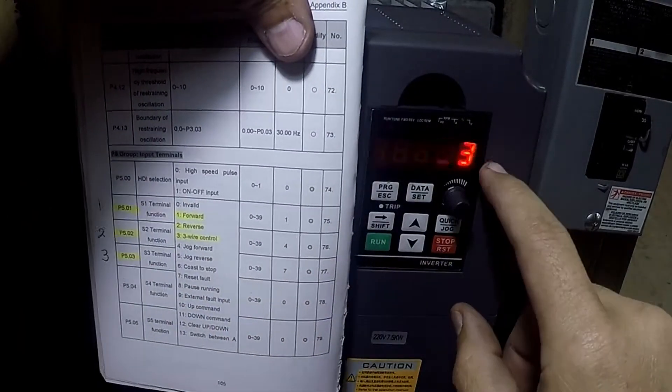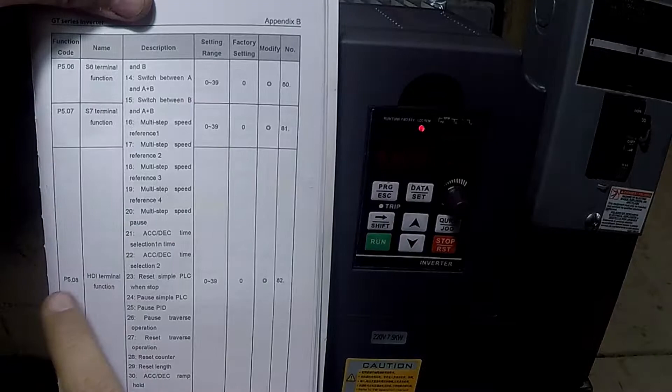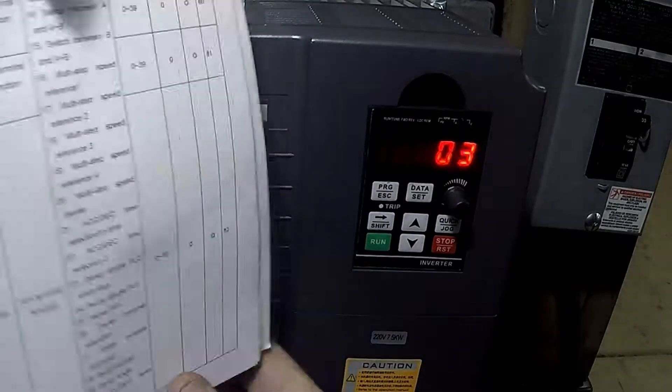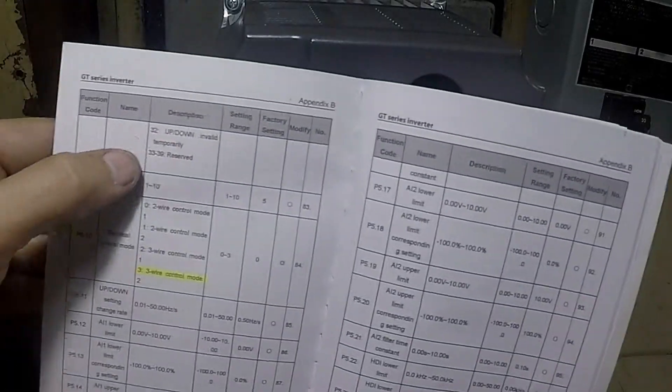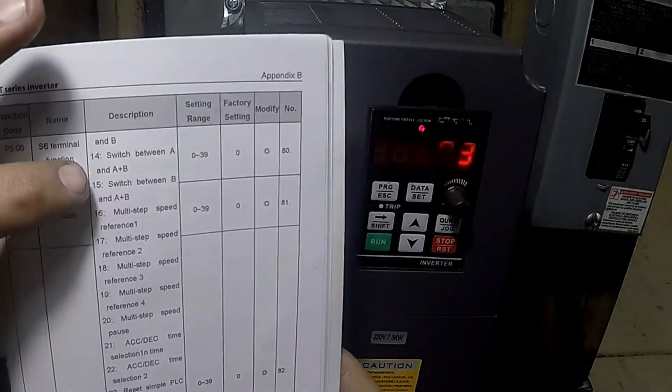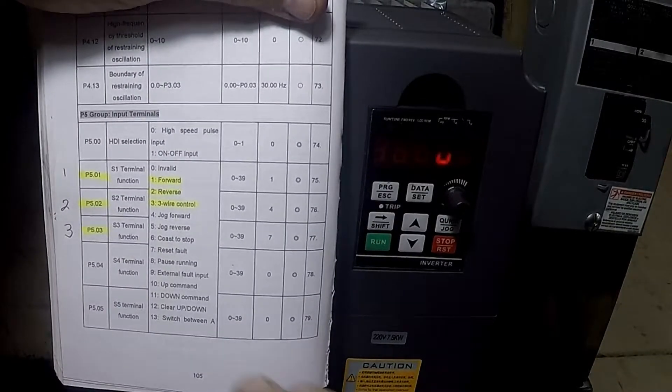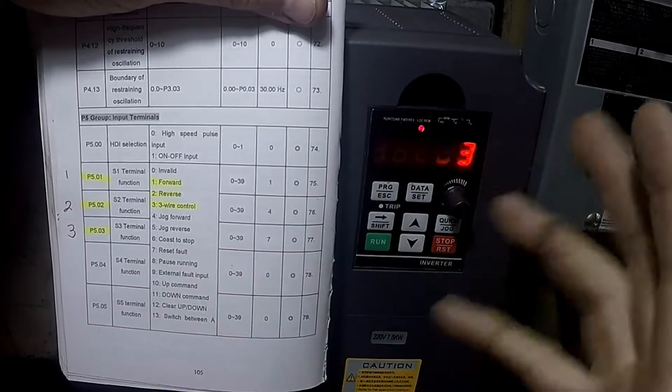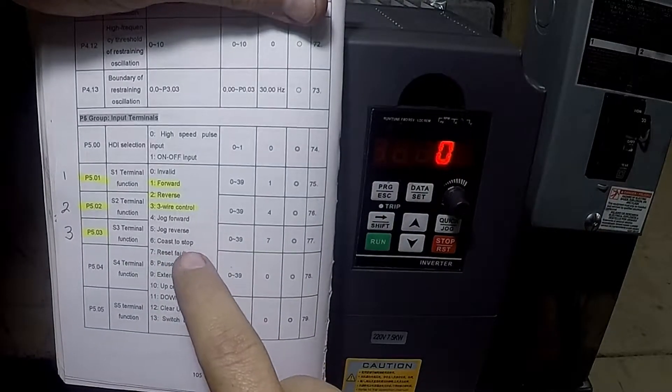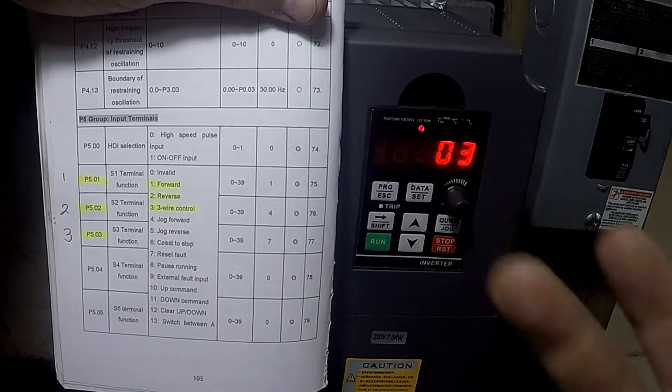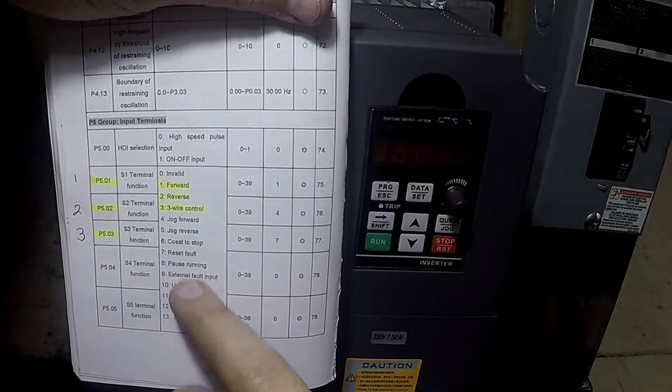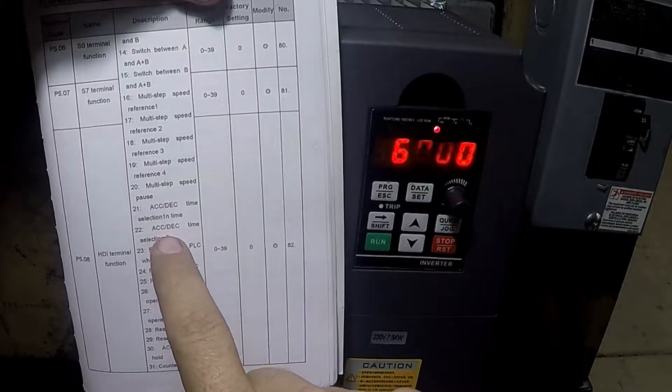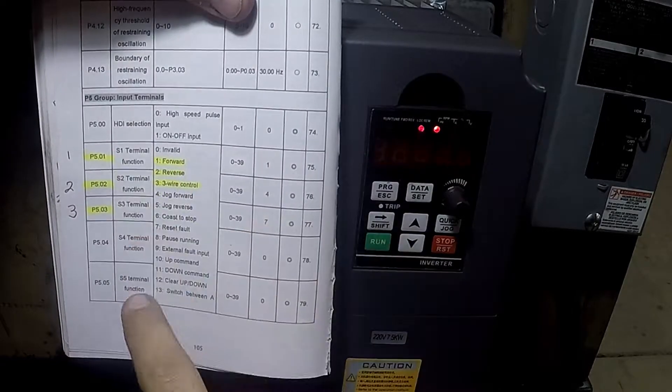So the way these parameters work - one, two, three, four, five, six, seven and eight can all be set to any number between zero and up to 32, 33. Each of those numbers assigns a different thing to that specific terminal. So I only use the first three terminals and I set those to forward, reverse, and three wire. If you have more buttons and you need to wire up maybe some jog buttons so you can go a little bit faster or slower, if you have a braking resistor in your VFD, you might want to set up a coast to stop versus a braking stop. If you want to set up some speed control, there's options for doing that in some of these as well. You can change acceleration, deceleration time - all those parameters you can set to a button that's attached to one of those terminals.